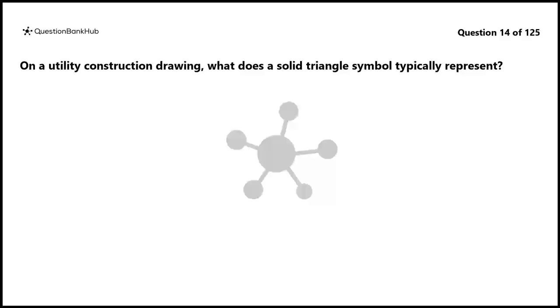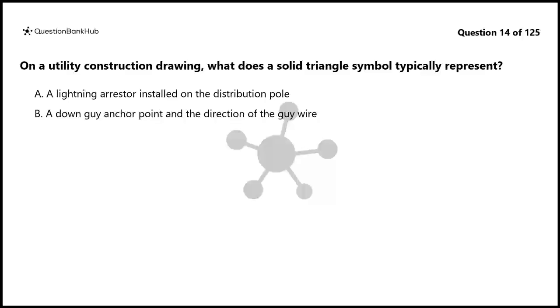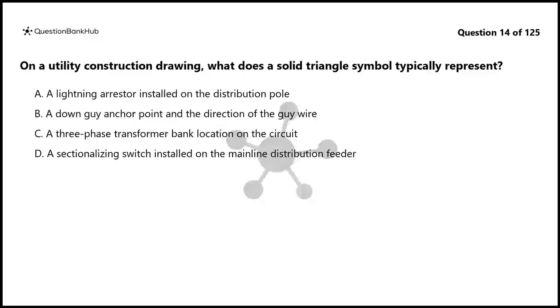Question 14. On a utility construction drawing, what does a solid triangle symbol typically represent? A. A lightning arrestor installed on the distribution pole. B. A down guy anchor point and the direction of the guy wire. C. A three-phase transformer bank location on the circuit. D. A sectionalizing switch installed on the mainline distribution feeder.